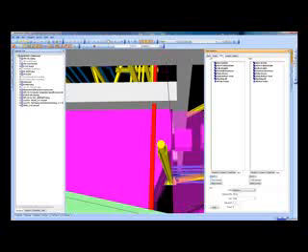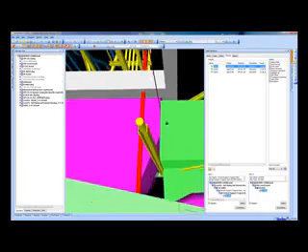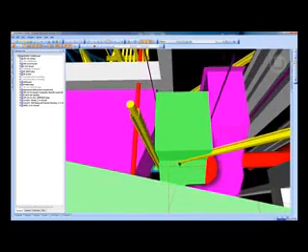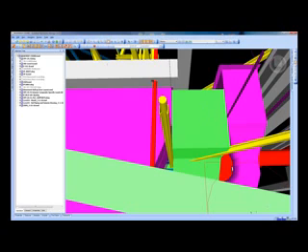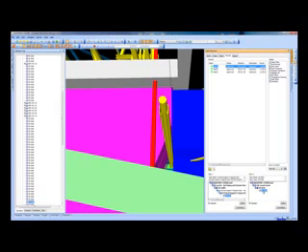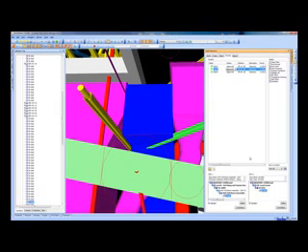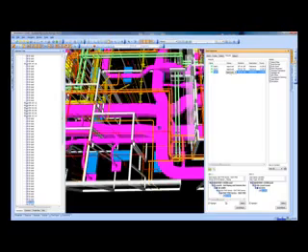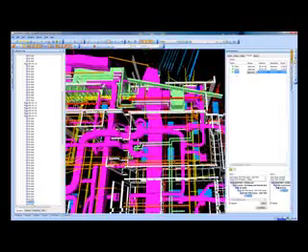So here's our clash detection, and we'll get our different trades together, and so we'll clash against the refrigeration piping and the mechanical. I have it set up previously, so once we would hit start, we go to the results, and it shows us a camera view of every clash. And this is a clash between that strut down below and this access region, which we can see here in solid. There's another clash between another strut and the same access region, and I've approved these because in this case I asked the other trades if this was acceptable, and this also allows us to have a record of what happened so that no one has any questions.